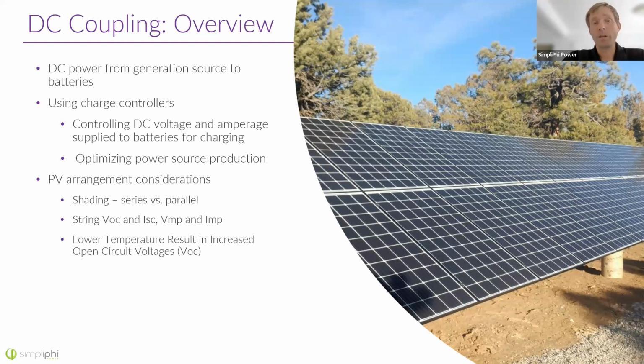There are a lot of arrangement considerations for PV panels. You want to make sure that you're not going to have shading issues with your array. You want to decide how many panels to put in series, how many you're going to have per string, and how many you are going to have in parallel. When you parallel your panels, you increase the current. When you put your panels in series, you increase the voltage, and there are limitations with equipment. So you have to design those arrays consistent with the equipment that you'll be using.